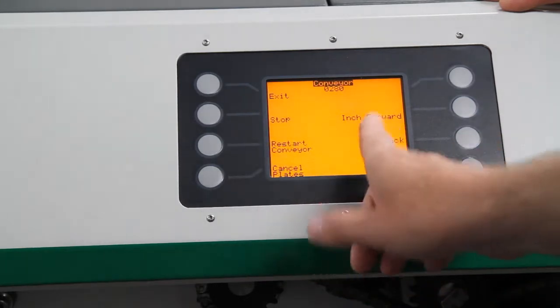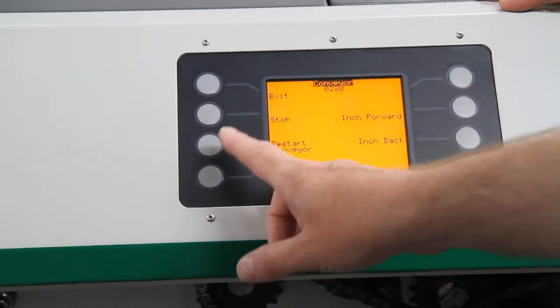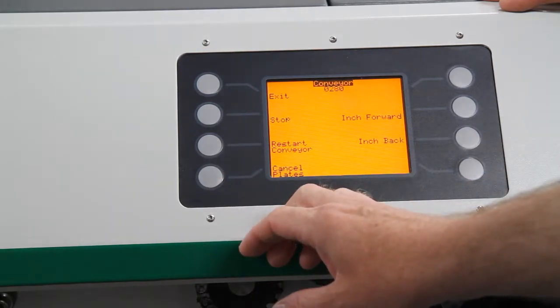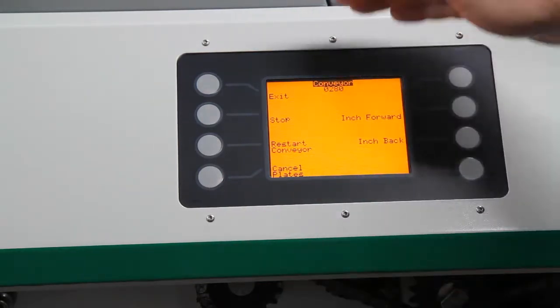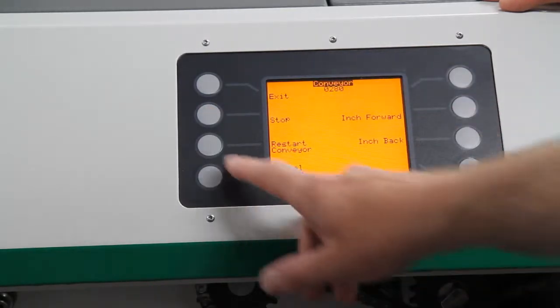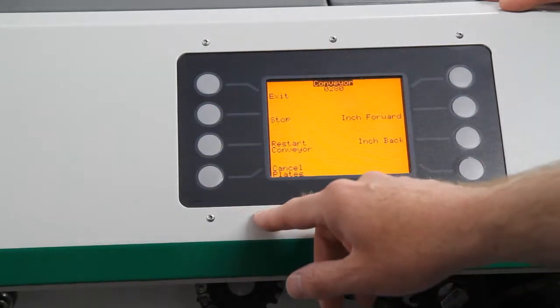Oh right. But if you're going to inch forward and inch back, you need to stop the conveyor first and then restart it afterwards. So you've had a plate jam. Come into this screen, press the stop button, inch forward, inch backwards, and then reset it. Come out of it, restart conveyor.